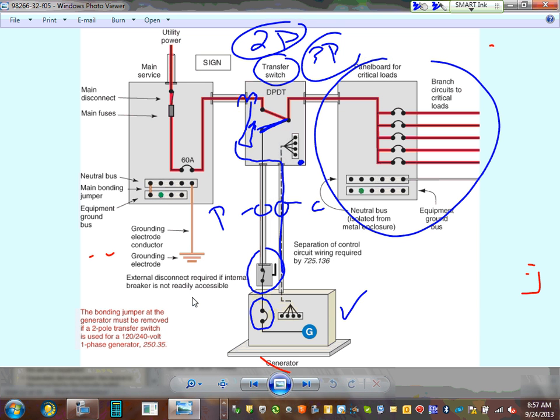You need three poles, one for the neutral. You don't want to switch the neutral? Then it's a non-separately derived system. How many poles do you need? Two. Any comments, guys? Any questions about this? Now, this is a permanently installed generator.